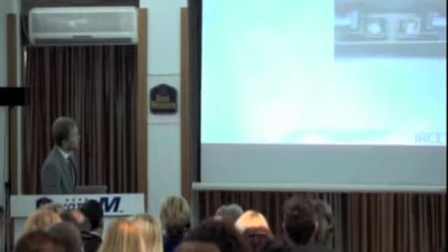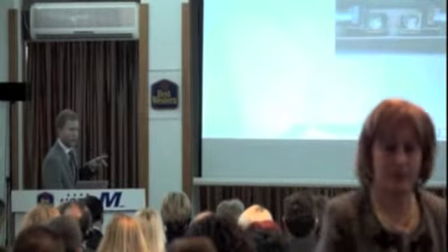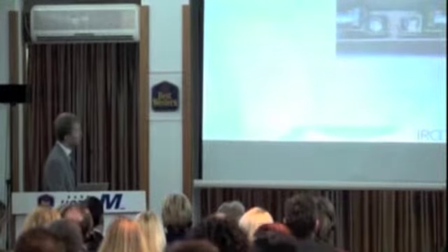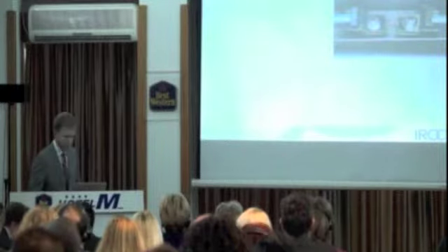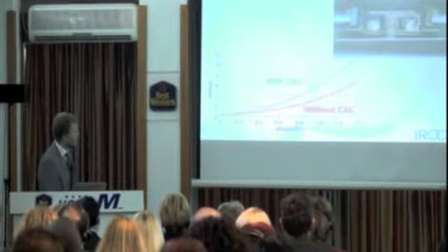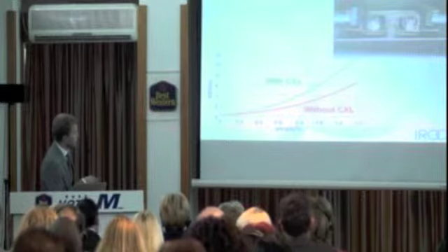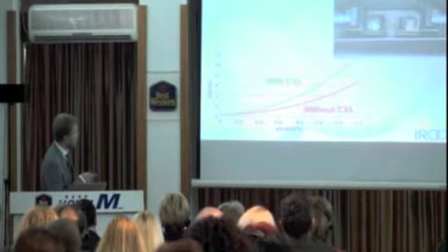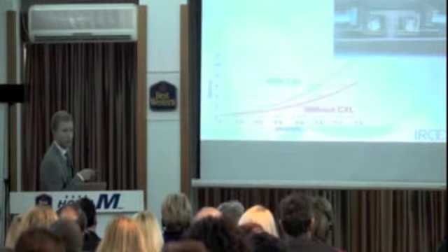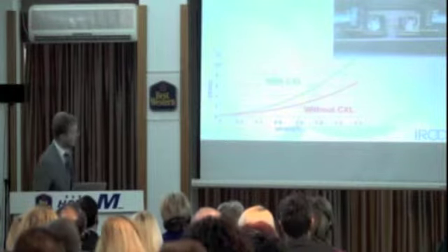This is a typical stress-strain apparatus. We can see the cornea strip that was excised from the cornea with a width of 5 millimeters. This is then clamped between 2 jaws and stressed until a strain of 12% of its original length. The stress is continuously measured of the cornea strip, which leads us then to such a stress-strain relation. We can see that without the crosslinking, we do have lower stress values than with crosslinking. This was made in porcine corneas, where we just receive a factor of 2 for stiffening.